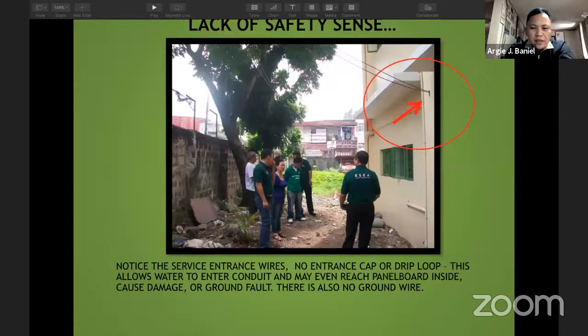Notice the service entrance wire has no entrance cap or drip loop. There is no entrance cap on the part in red. This allows water to enter the conduit and may even reach the panel board inside, and it will cause damage or ground fault. There is also no ground wire. We have had many fire incidents where this is what commonly happened, because the drip loop is the protection that keeps water from entering. But here, as we can notice, water gets in until it fills up.